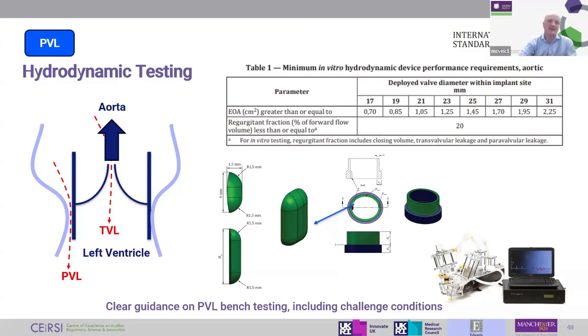I'll say in summary, as I mentioned, the testing serves three purposes. Design verification, obviously we've got to do that. Head-to-head testing, if we're comparing to a predicate device, that could be done. And validation of our models. I covered some of the standardized tests in 5840. They are standardized and they can be used for that purpose, and they're very important for that purpose.